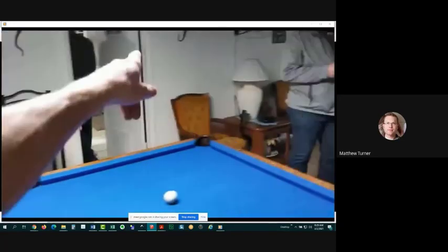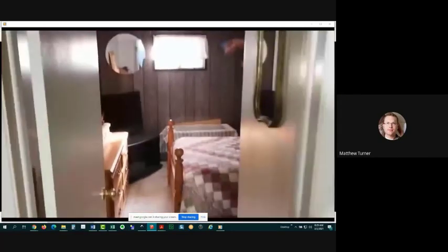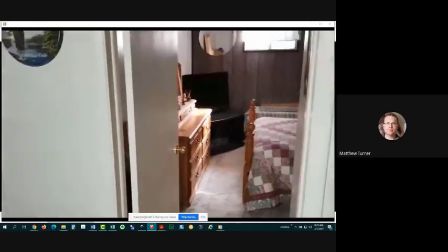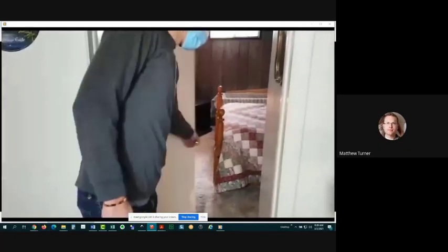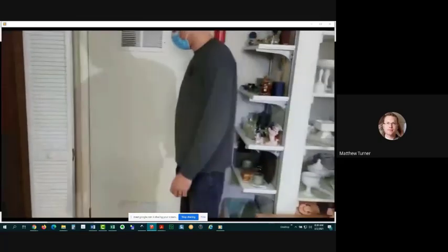Downstairs, we're going to have all these closet doors closed. But we do have one bedroom over here that we will close the door on, since there are no exhaust fans in there. And then we have one bathroom in here, and there is an exhaust fan in there, so we're going to leave that one open. So once we go back in here and close this closet door, then all of our interior doors and our closet doors are in the right position for the test.